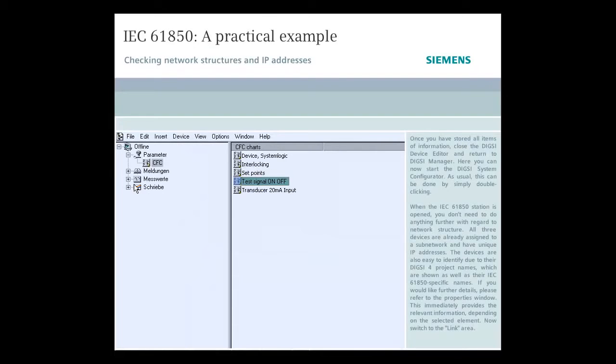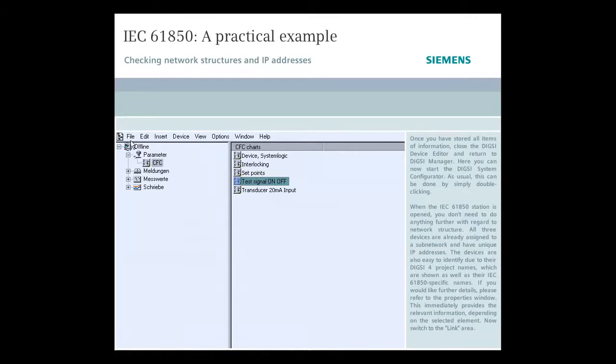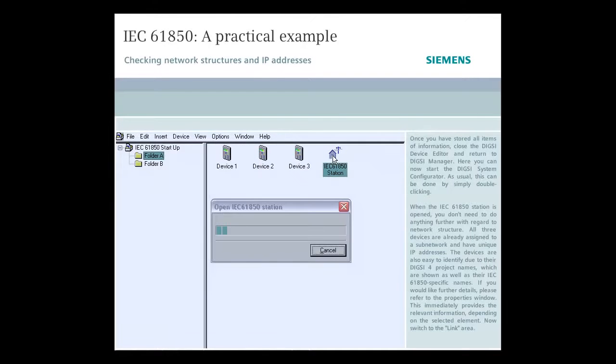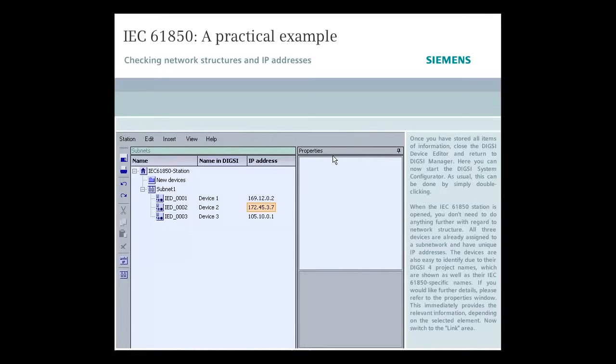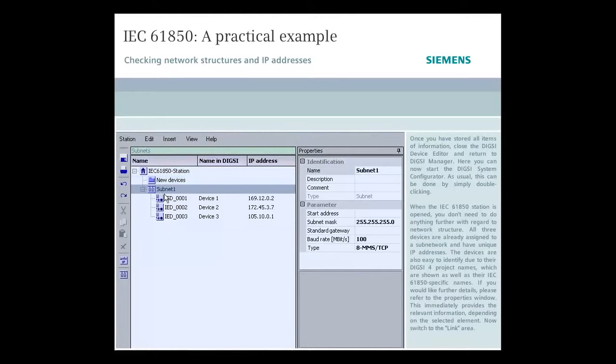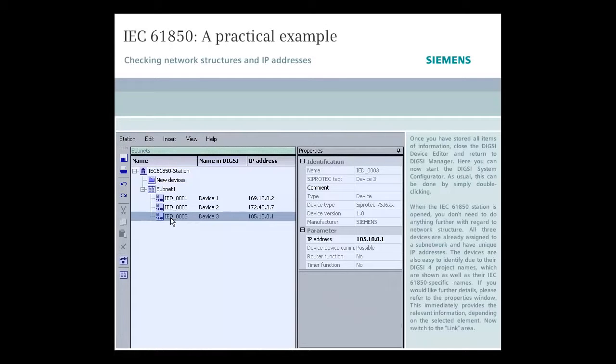Once you've stored all items of information, close the DIGSI device editor and return to DIGSI manager. Here you can now start the DIGSI system configurator. As usual, this can be done by simply double-clicking. When the IEC-61850 station is opened, you don't need to do anything further with regard to network structure. All three devices are already assigned to a sub-network and have unique IP addresses. The devices are also easy to identify due to their DIGSI 4 project names, which are shown as well as their IEC-61850 specific names. If you would like further details, please refer to the Properties window. This immediately provides the relevant information, depending on the selected element.